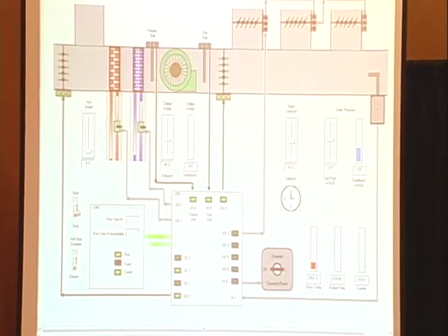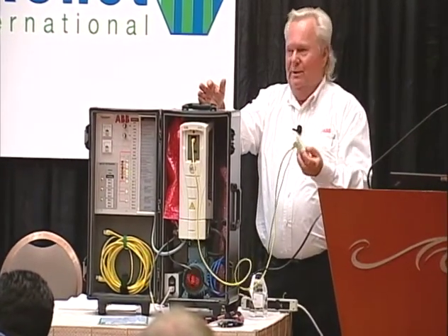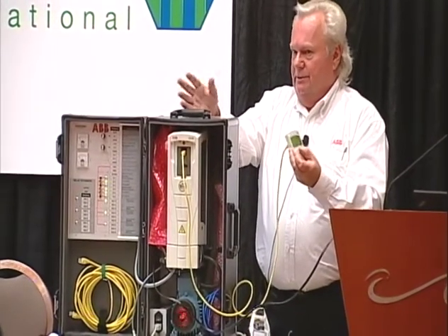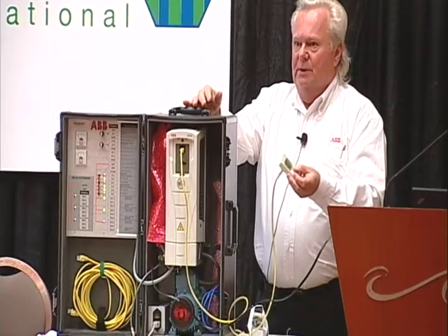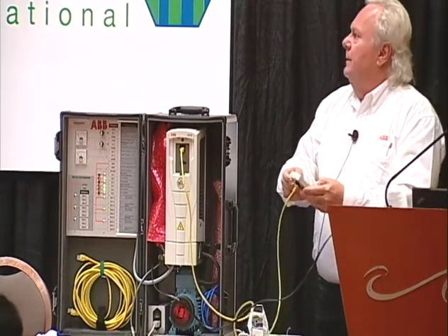So by using the building automation, but having the drive in the middle of the damper control and the damper proof, it keeps the owner from being able to blow up his ductwork by going to hand or bypass or something like that. So all these functions work in both hand or bypass. Okay, everybody with me? Go back to auto.